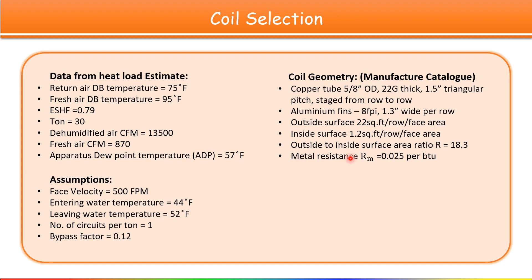Some data you will get from the manufacturer catalog, like metal resistance value — in our case 0.025 per BTU. Outside to inside surface area ratio is 18.3, inside surface is 1.2 square feet per row per face area, and outside surface is 22 square feet per row per face area.